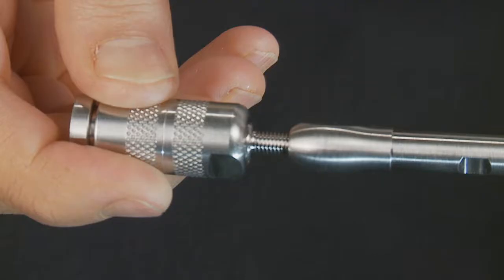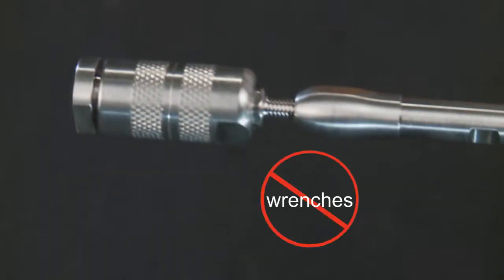In a clockwise direction, hand tighten the complete holder assembly onto the column. Do not use wrenches when connecting the Security Guard assembly to the column as it may cause assembly or column damage.